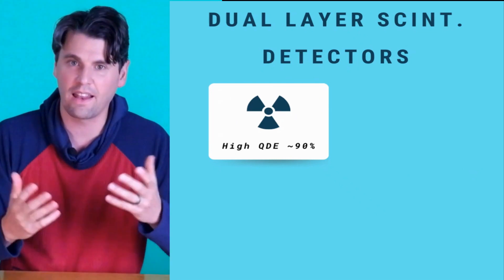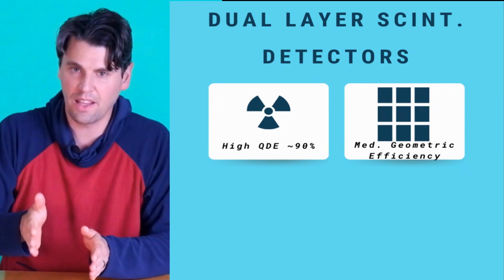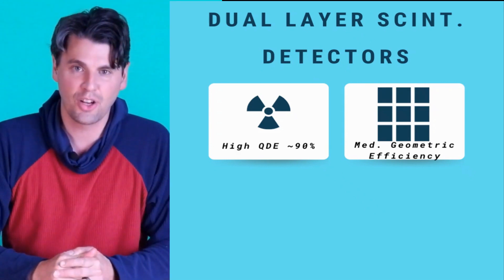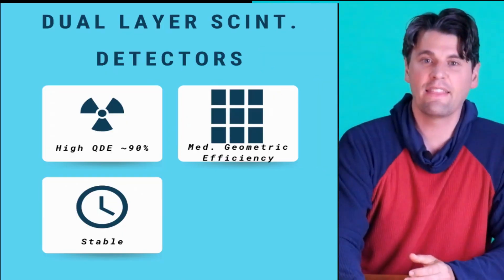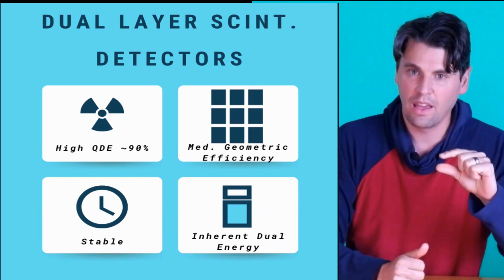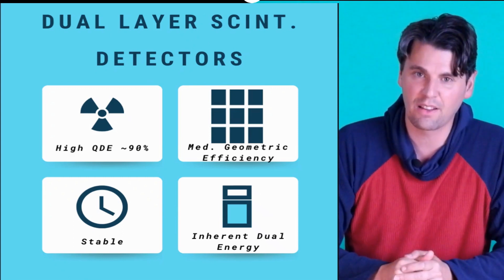Dual-layer scintillator detectors have high quantum detection efficiency because of those two scintillator layers, though geometric efficiency is slightly lower since the side-mounted photodiodes take up more space. These systems are very stable and have an inherent ability to perform dual-energy imaging, since the two readouts provide sensitivity to lower versus higher energy x-rays. Right now virtually all CT systems in the field use scintillator-based detectors. A handful of systems with photon-counting detectors are just coming to market — drop a comment if you'd like a video on that technology.